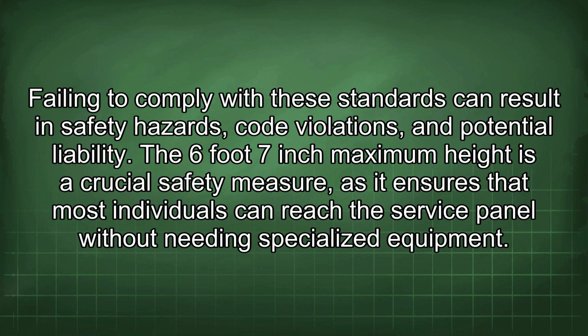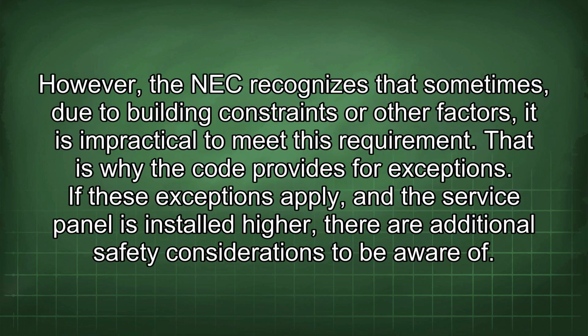The 6 foot 7 inch maximum height is a crucial safety measure, as it ensures that most individuals can reach the service panel without needing specialized equipment. However, the NEC recognizes that sometimes, due to building constraints or other factors, it is impractical to meet this requirement. That is why the code provides for exceptions. If these exceptions apply and the service panel is installed higher, there are additional safety considerations to be aware of.